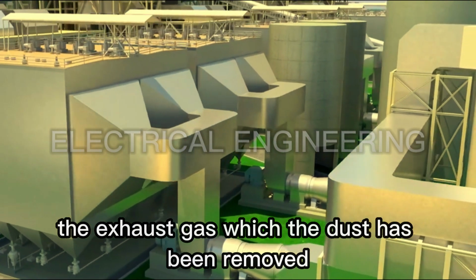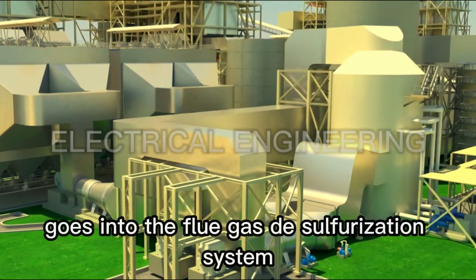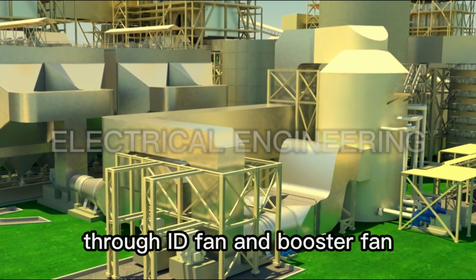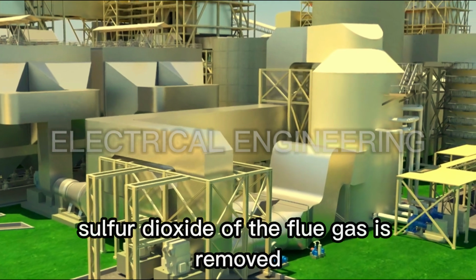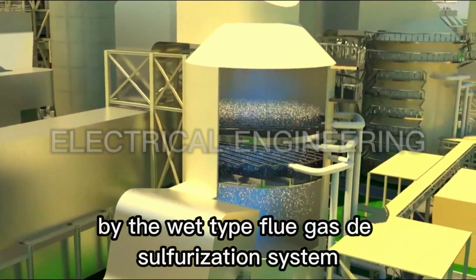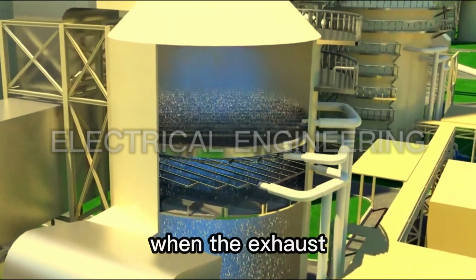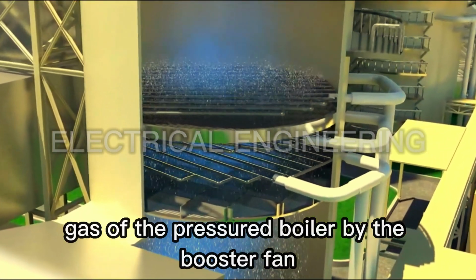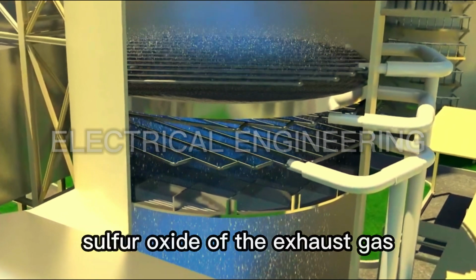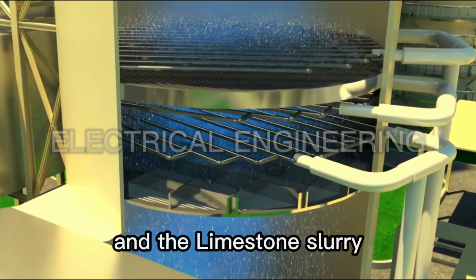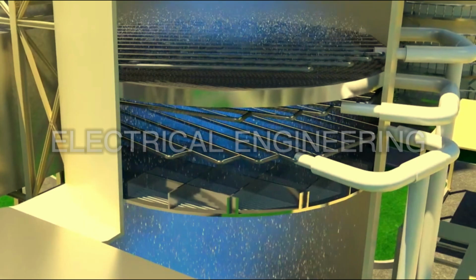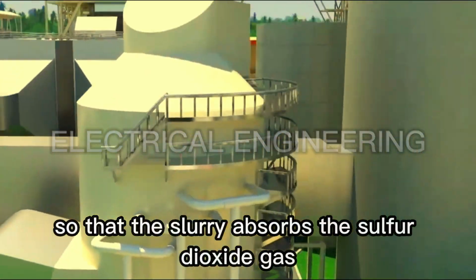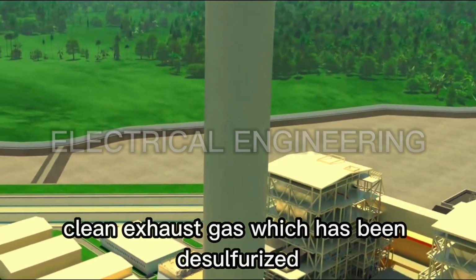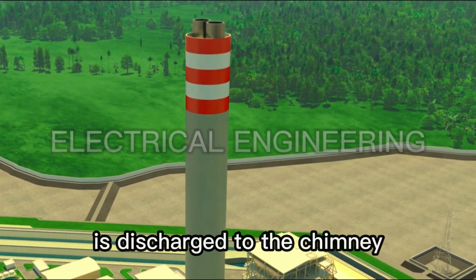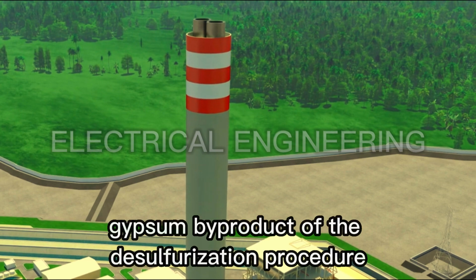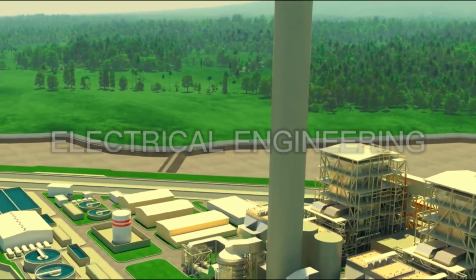The exhaust gas, from which the dust has been removed, goes into the flue gas desulfurization system through the ID fan and booster fan. Sulfur dioxide of the flue gas is removed by the wet-type flue gas desulfurization system when the exhaust gas, pressured by the booster fan, goes through the absorption tower. Sulfur oxide of the exhaust gas and the limestone slurry, which is sprayed from the top of the absorption tower, react to each other so that the slurry absorbs the sulfur dioxide gas. Clean exhaust gas, which has been desulfurized, is discharged to the chimney, and gypsum is generated as a byproduct of the desulfurization procedure.